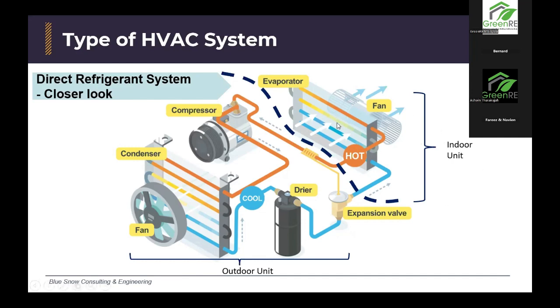So the hot refrigerant goes to the compressor. In this system the refrigerant can exist in two conditions, gas and liquid, and it can also be a mixture of gas and liquid. So before the refrigerant goes into the compressor, the refrigerant needs to be 100% gas, because the compressor cannot stand any liquid and it can harm the compressor system. So when the gas refrigerant goes into the compressor, it gets compressed and becomes high pressure and high temperature. So the temperature here is increased a lot compared to when it left the evaporator.